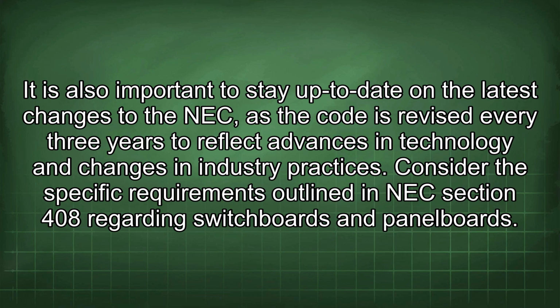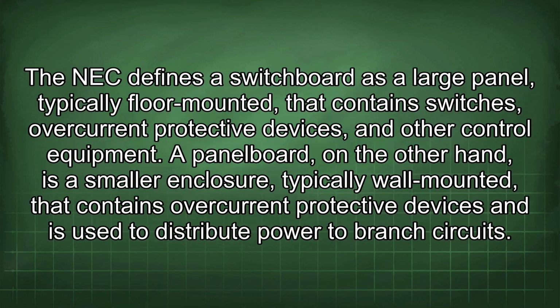Consider the specific requirements outlined in NEC section 408 regarding switchboards and panel boards. The NEC defines a switchboard as a large panel, typically floor-mounted, that contains switches, overcurrent protective devices, and other control equipment. A panel board, on the other hand, is a smaller enclosure, typically wall-mounted, that contains overcurrent protective devices and is used to distribute power to branch circuits.